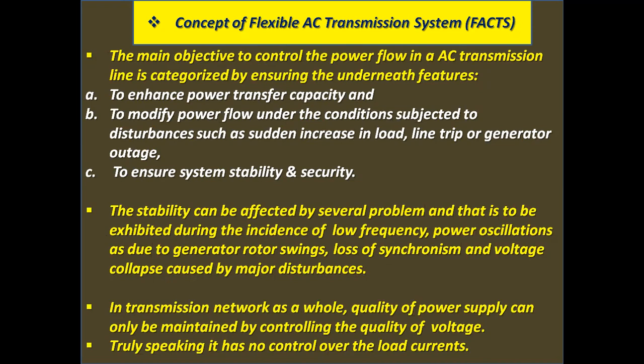Concept of flexible AC transmission system, which is called FACTS, flexible AC transmission system. The main objective to control the power flow in an AC transmission line is characterized by ensuring the underneath features. A, to enhance power transfer capacity and to modify power flow under the conditions subjected to disturbances such as sudden increase in load, line trip, or generator outage. And C, to ensure system stability and security.